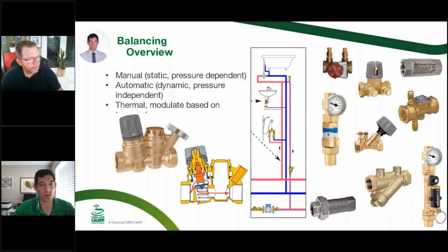So the way this works with thermal disinfection is there's a second cartridge that can be opened with 24 volts, or there's an option to have a thermal cartridge that, when it sees a certain temperature, opens a bigger orifice and lets that hot water through the risers to complete the thermal disinfection, and then it falls back into normal operation. So kind of a multi-use valve.